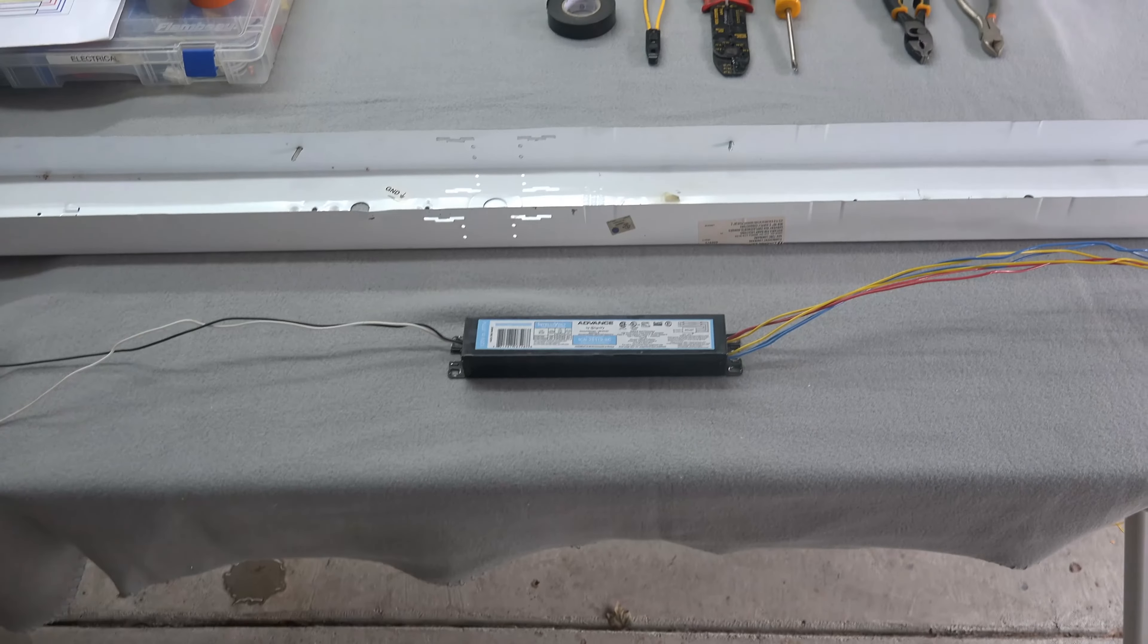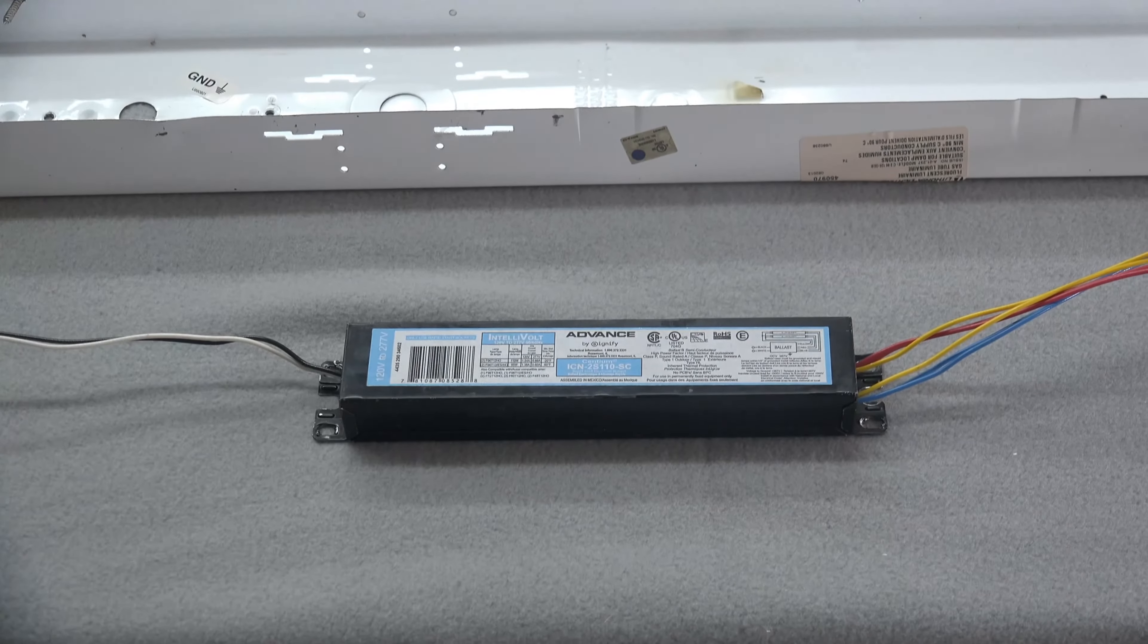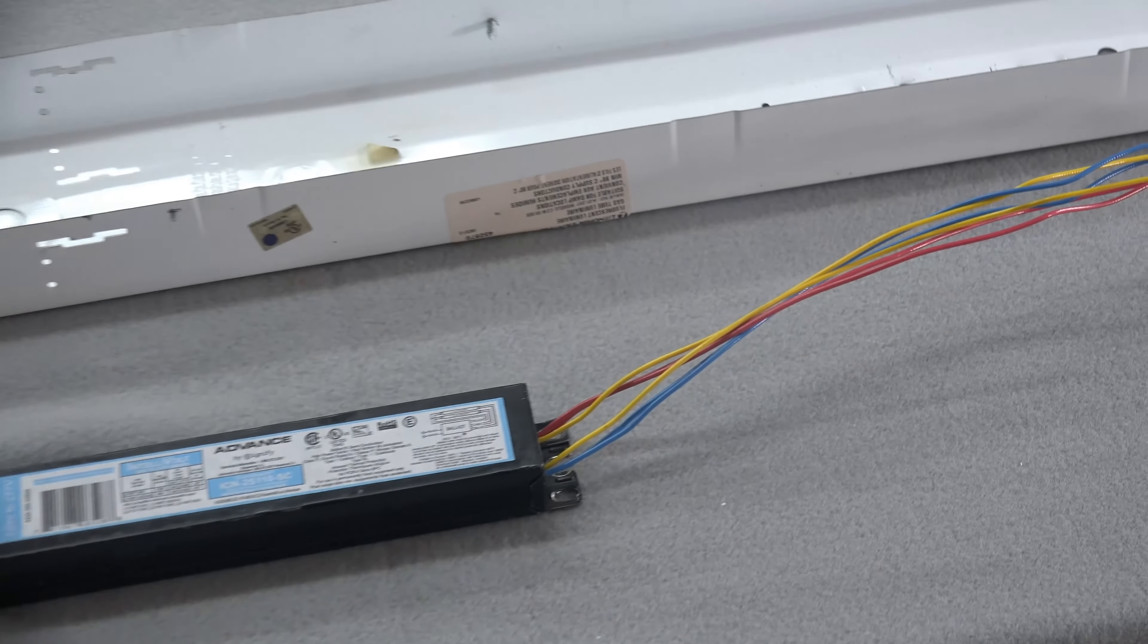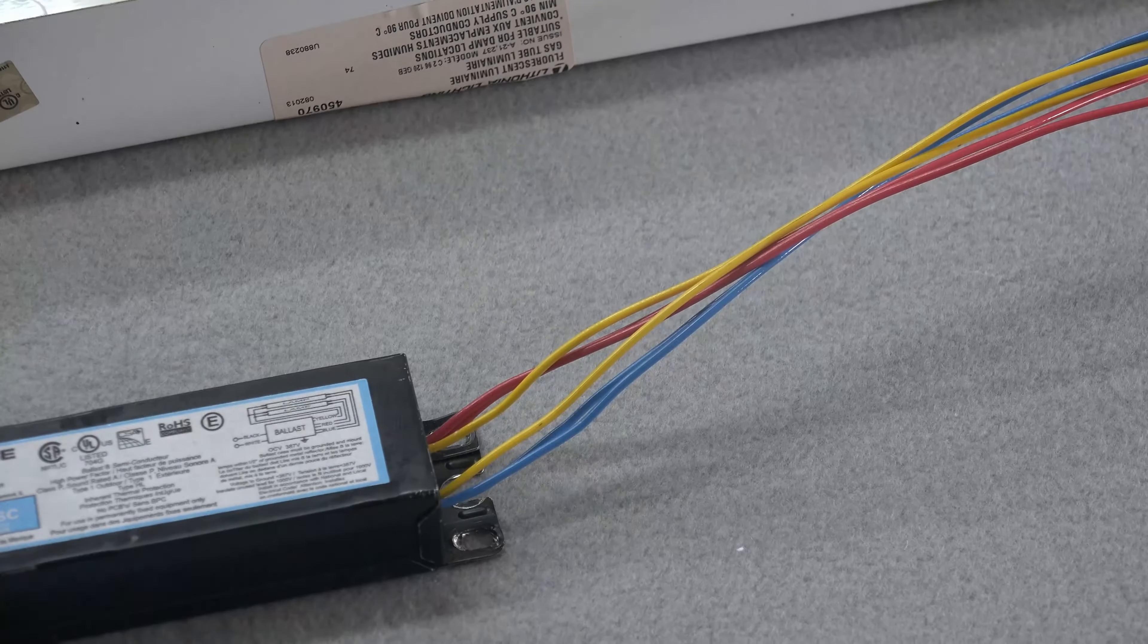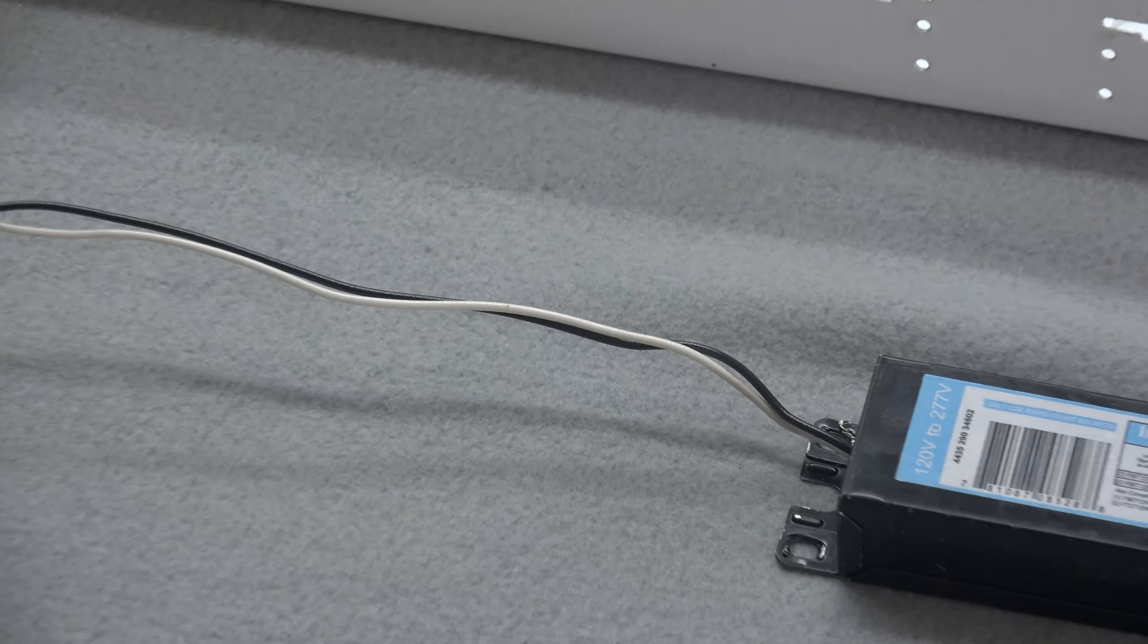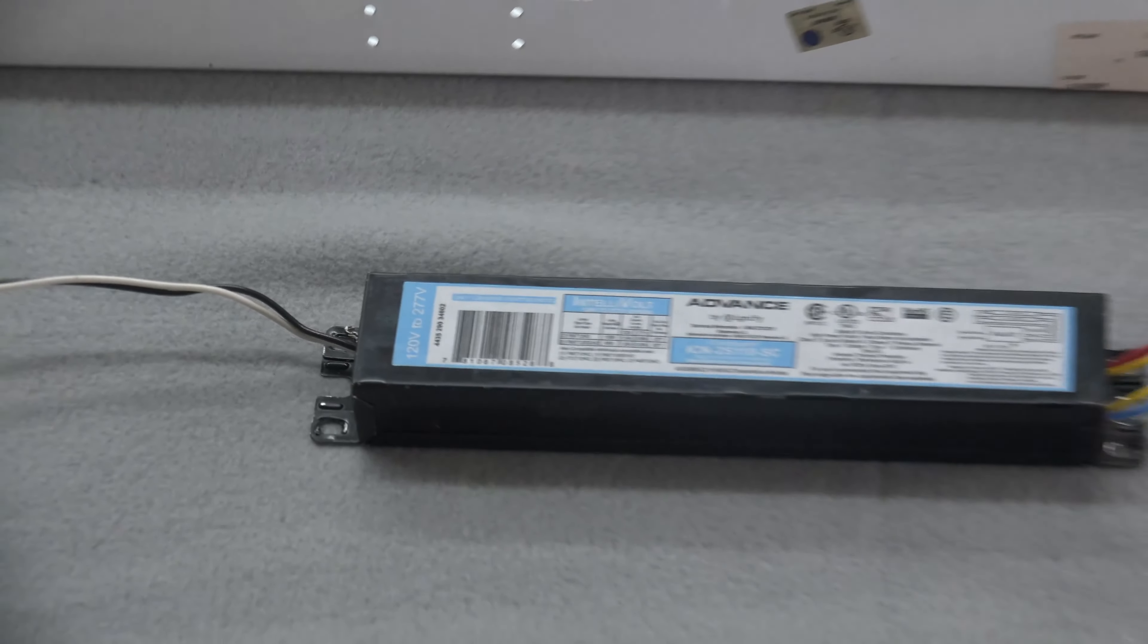Looking at your new ballast, there are now eight wires for a two-lamp setup. You have a red and a blue for each bulb, and you have a yellow which is your common wire. On the other side you have a white and a black. Your black wire is your hot wire or power wire, and your white is your neutral.